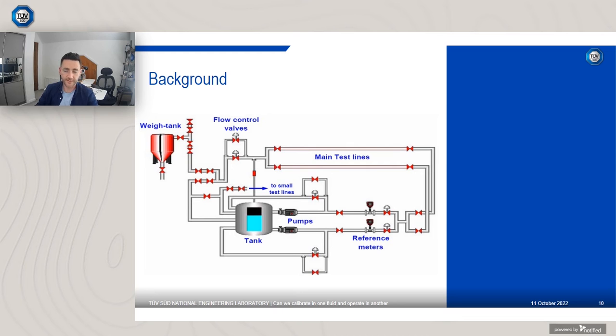Don't have quite as nice a schematic for this one, but this is our national standard for oil flow. It has a gravimetric primary system, which is this weigh tank system here. We actually have 4 of varying different sizes depending upon the flow rate at which we're operating. We use positive displacement reference meters. So these are pre-calibrated against the weigh tank for a given viscosity and temperature. So we can operate start-stop, basically that's flowing through into the weigh tank, or we can operate in recirculation mode using these master meters that are pre-calibrated.